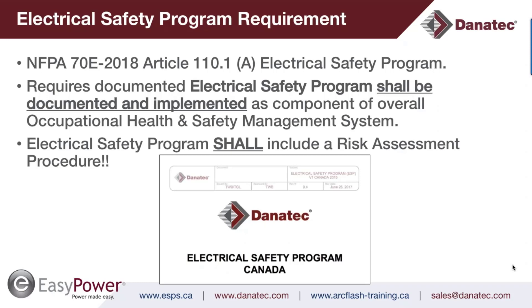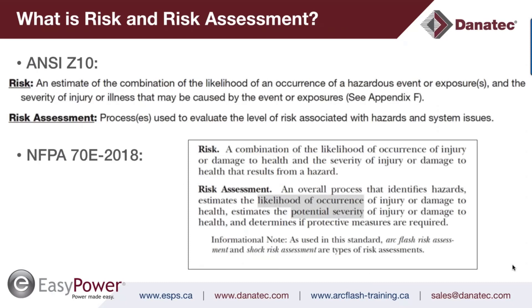Your electrical safety program should identify the risk assessment procedure requirement and provide a process to document discrete energized electrical work task risk assessments. ANSI Z10 is the occupational health and safety management system standard for the United States; in Canada we have CSA Z1000. ANSI Z10 defines risk as an estimate of the combination of likelihood of occurrence of a hazard event or exposure, and the severity of injury or illness caused by that event or exposure.